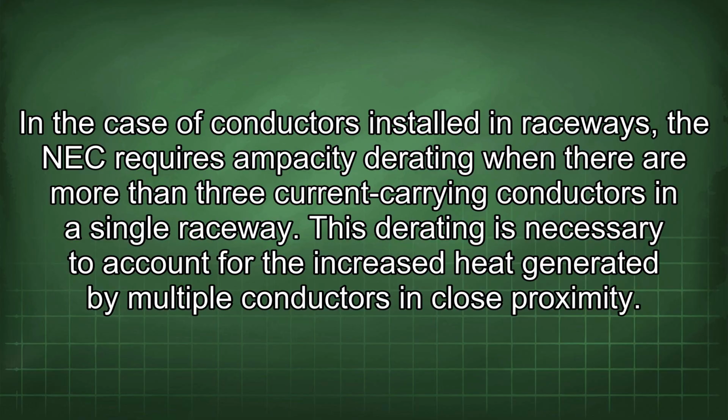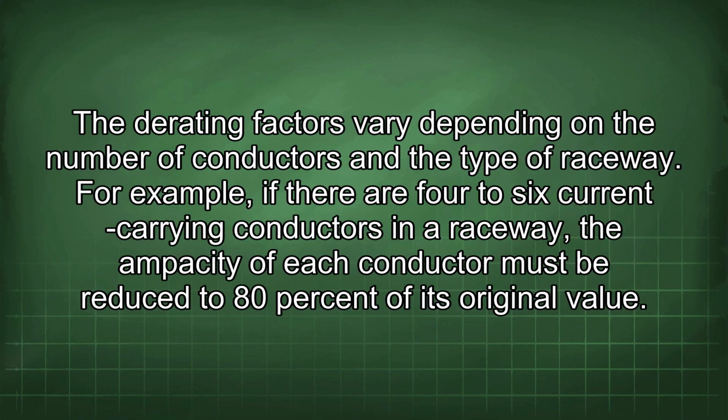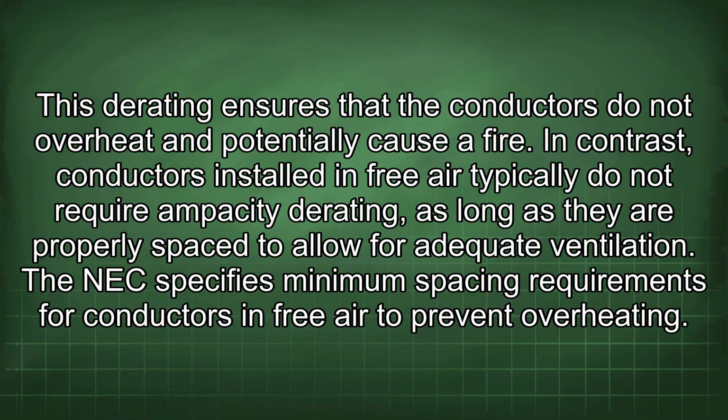This adjustment is necessary to account for the increased heat generated by multiple conductors in close proximity. The adjustment factors vary depending on the number of conductors and the type of raceway. For example, if there are 4 to 6 current-carrying conductors in a raceway, the ampacity of each conductor must be reduced to 80% of its original value. This ensures that the conductors do not overheat and potentially cause a fire.